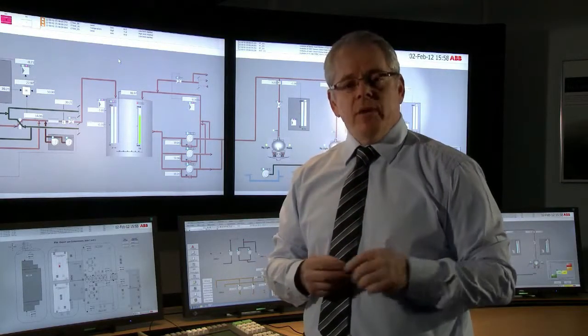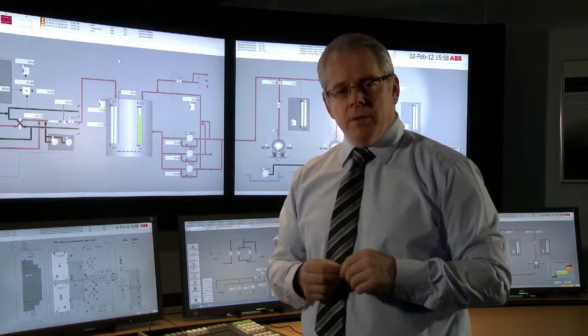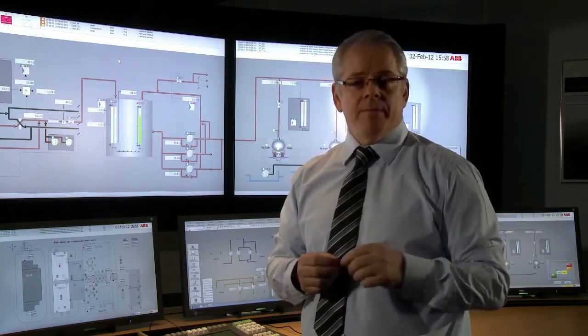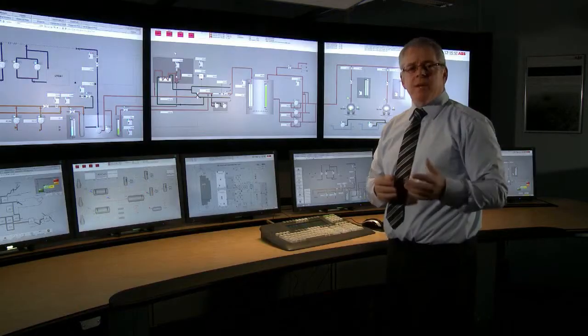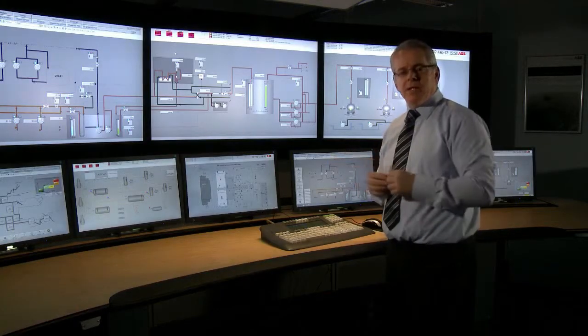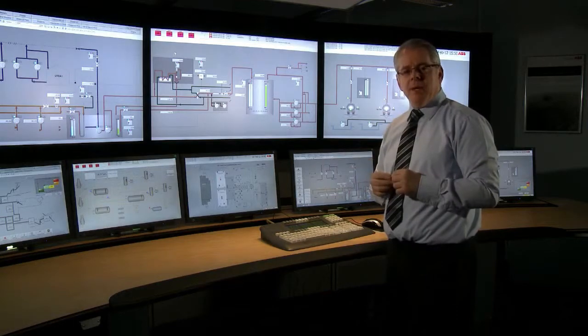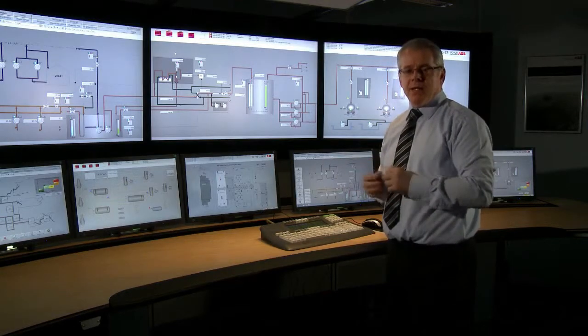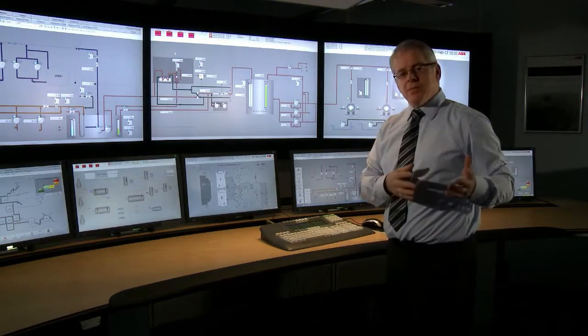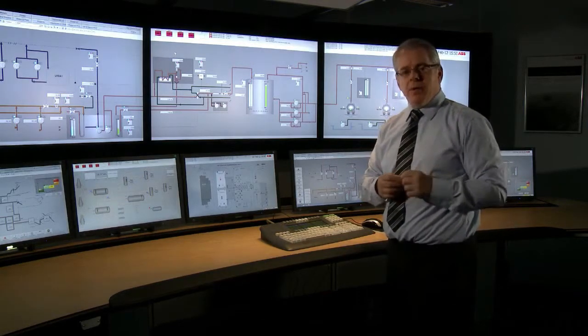800XA now more closely follows the EEMUA 191 guideline than ever before, and we do that by bringing a lot of the alarm management functionality inside of 800XA, so third-party systems are no longer required.